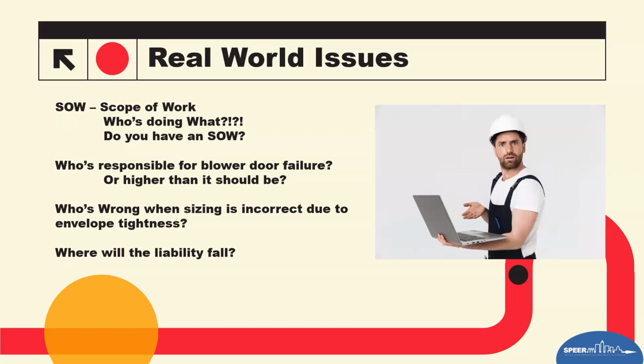So there'll be things that the building department thinks is being done, or that every system is being tested, but LEED, NGBS, and HERS can also still allow for a sampling protocol, which means now not every unit's being tested and or verified. So having a scope of work and having a conversation with a third party to get a scope of work could ensure that all T's are crossed, all I's are dotted, making sure everything gets verified. So having a SOW in the builder's packet telling the builder or the developer what is and isn't expected to be verified by the third party is a great way to do it.